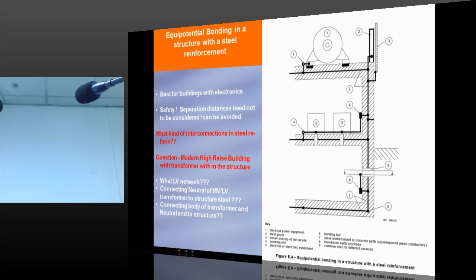LEMP, lightning electromagnetic pulse. Just for your information, you imagine that an apparatus which is here and this place is not connected. I mean, the connection number 4, a bonding connection between the apparatus, the PE conductor and the reinforcement. It is not connected. What will happen? Depending upon the sensitivity of the equipment and the PE conductor length and the power line conductor length, there can be loop currents which will destroy your electronics. So to make a 100% perfect installation, you need to refer to the other standards, the EMC standards, the 61000-4 series, which explains this phenomenon in a better way.